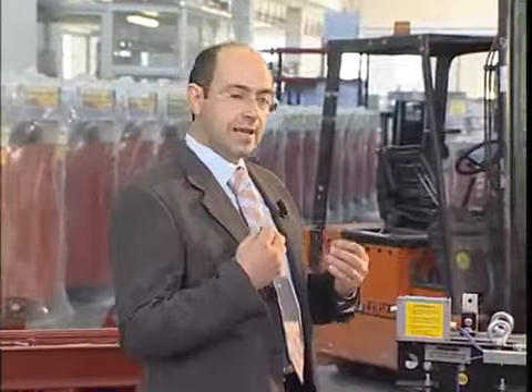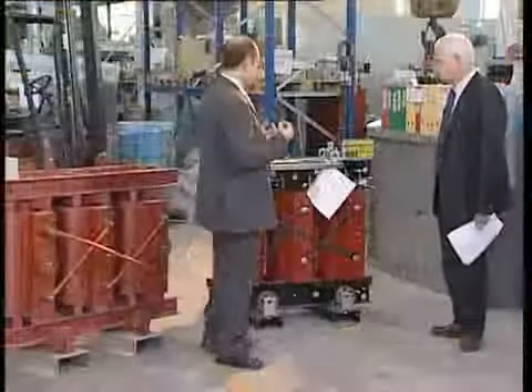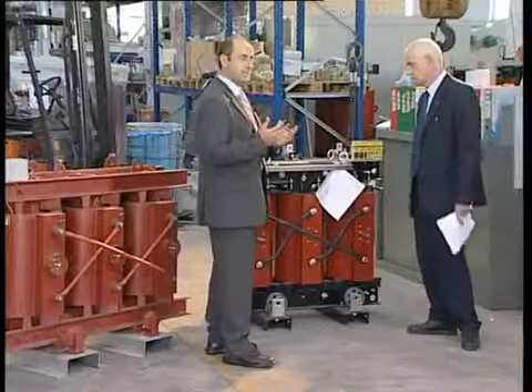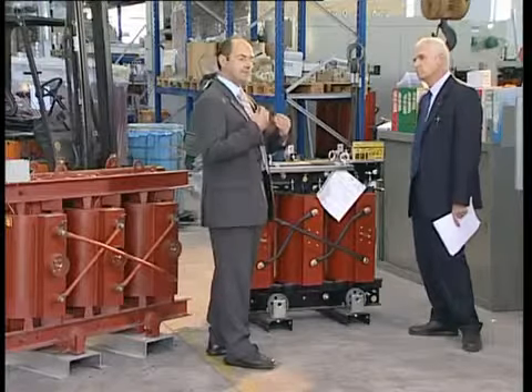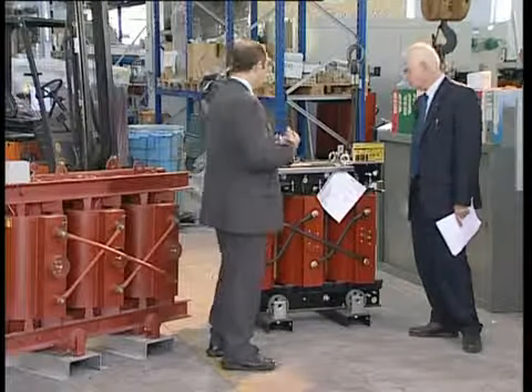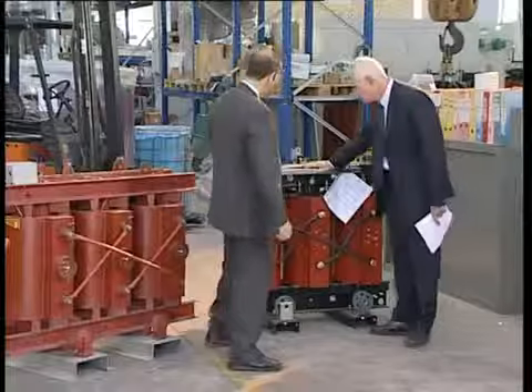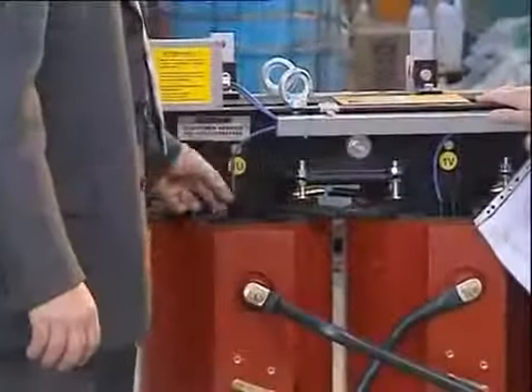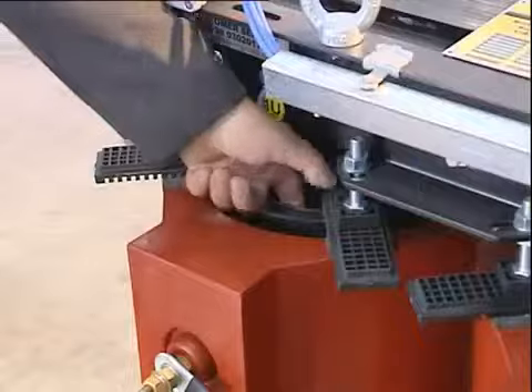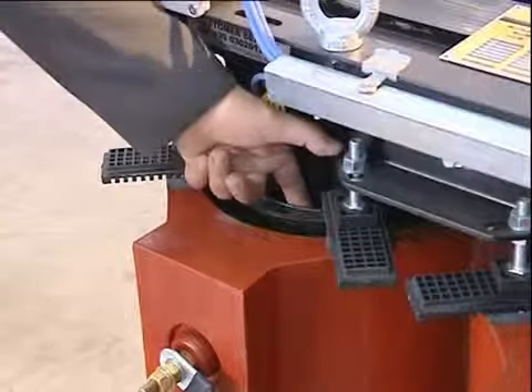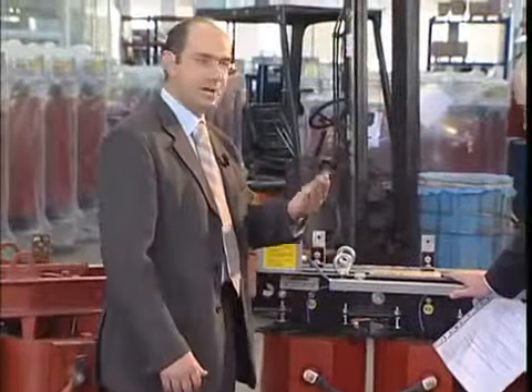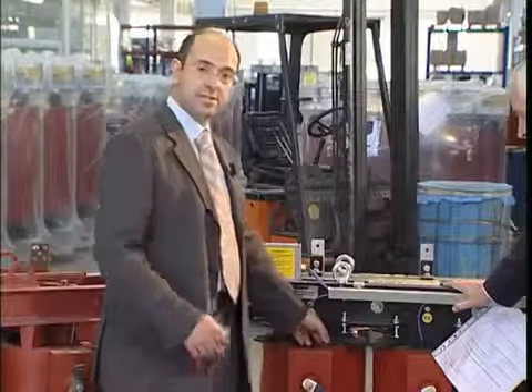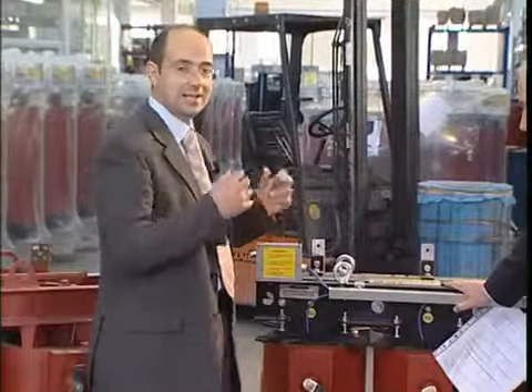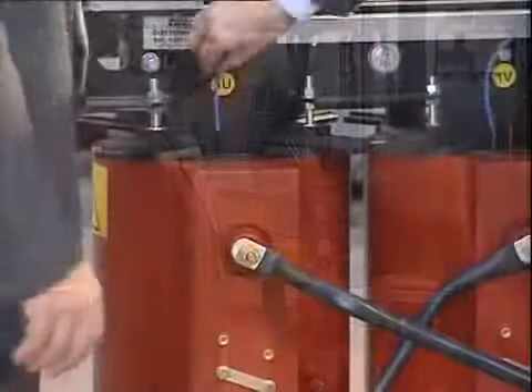Any other aspects? The time has come to deal with another aspect characterizing the reliability of a resin-insulated transformer. The transformer's ability to dispose of the losses it produces and, therefore, to preserve the material's insulating capacity over time. What are our transformer's peculiar features? We can see that our transformer has considerably large ventilation ducts, to the point that I can insert my fingers, whose diameter exceeds 1 centimeter, into them. This allows for an easy outflow of hot air and, consequently, ensures easy transformer cooling.